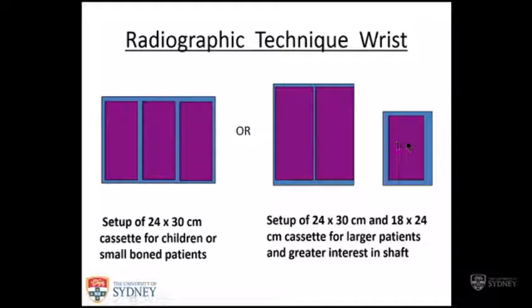And you pick a lateral for that. But what happens is, when this cassette is read, whatever program you pick, whatever body part you pick for its algorithm, the program will try and optimise all the information on the entire cassette. And so it will average out the best appearance for the three things. And that's fine, it'll work well.